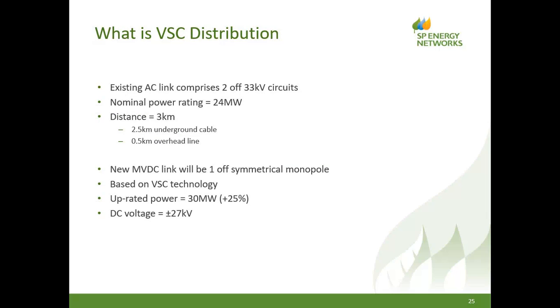We will take two existing 33 kV AC circuits with a nominal power rating of 24 megawatts and convert them to operate as DC. Kevin's explained the cable and overhead lines. I want to talk about that. But what we're going to do is build a MVDC link, which will operate as a single symmetrical monopole. I'll explain this in a few seconds. And this will be based on voltage source converter technology. So this is the most appropriate technology for this type of medium voltage DC application. And again, I'll discuss that in a few moments.